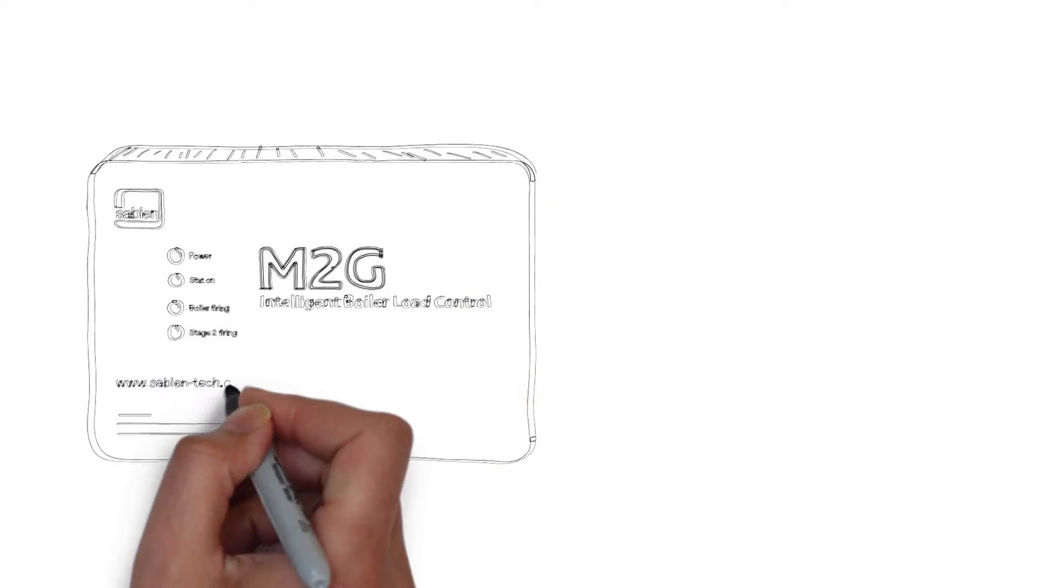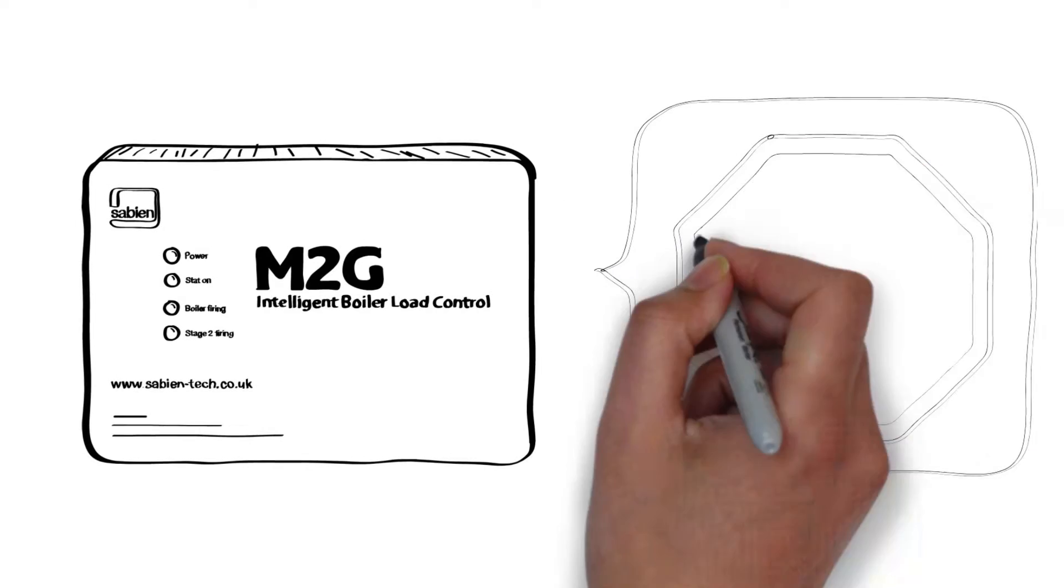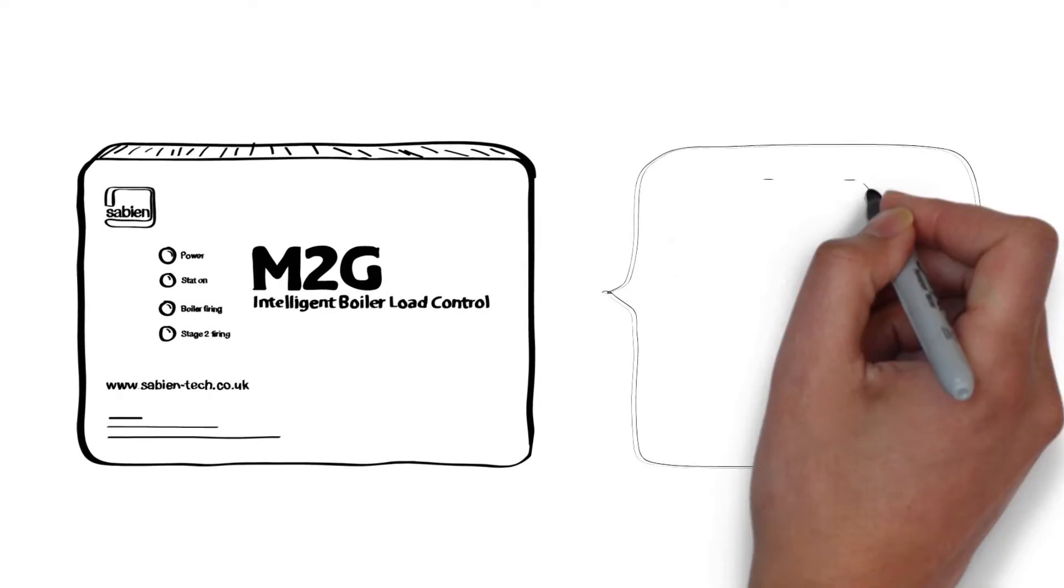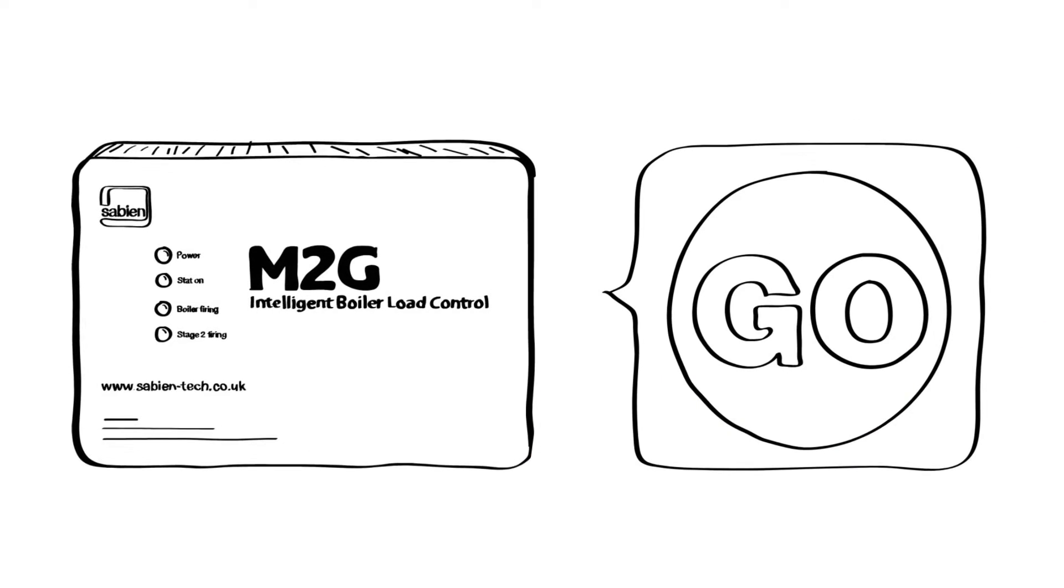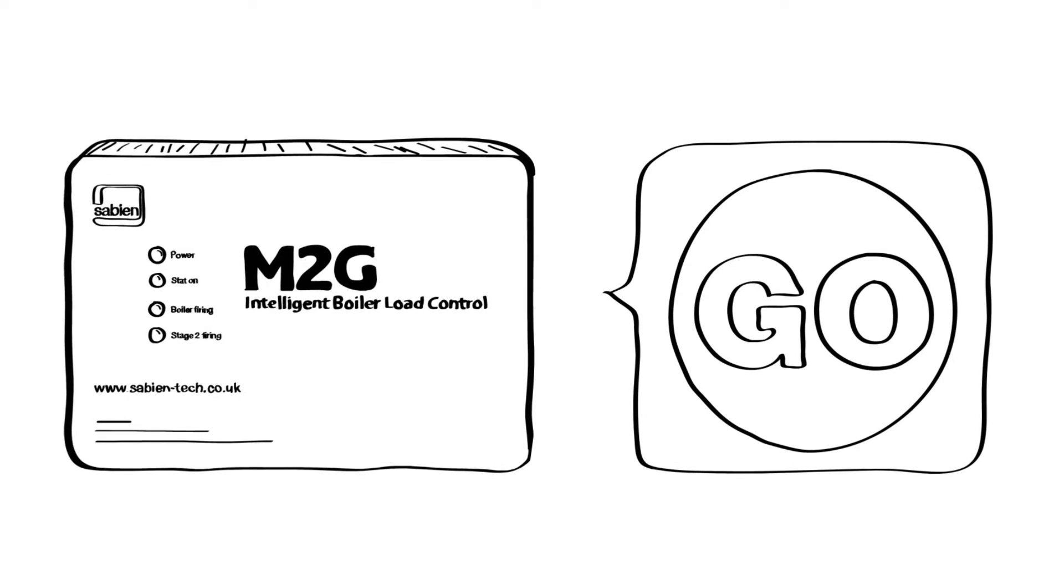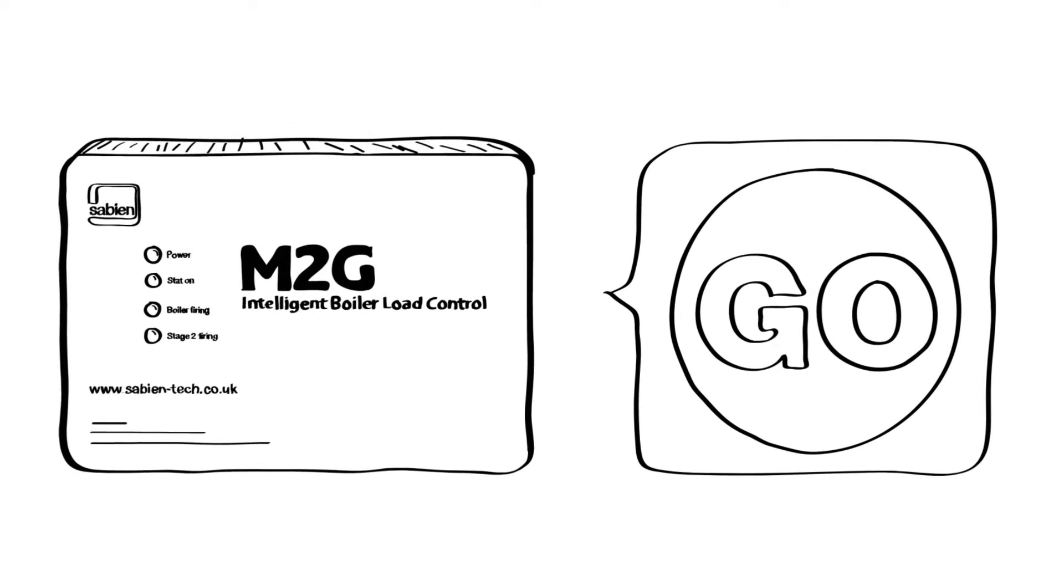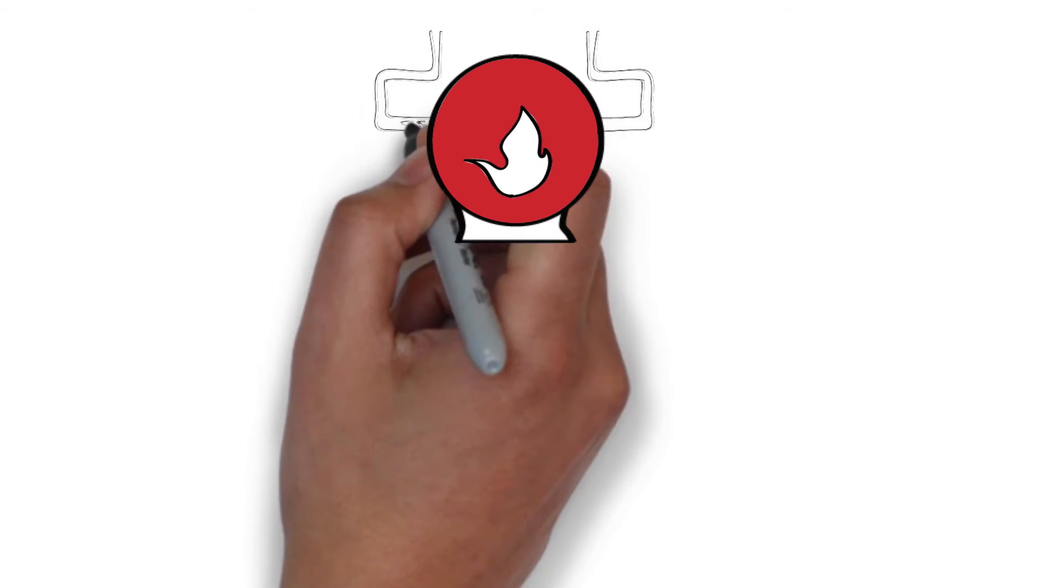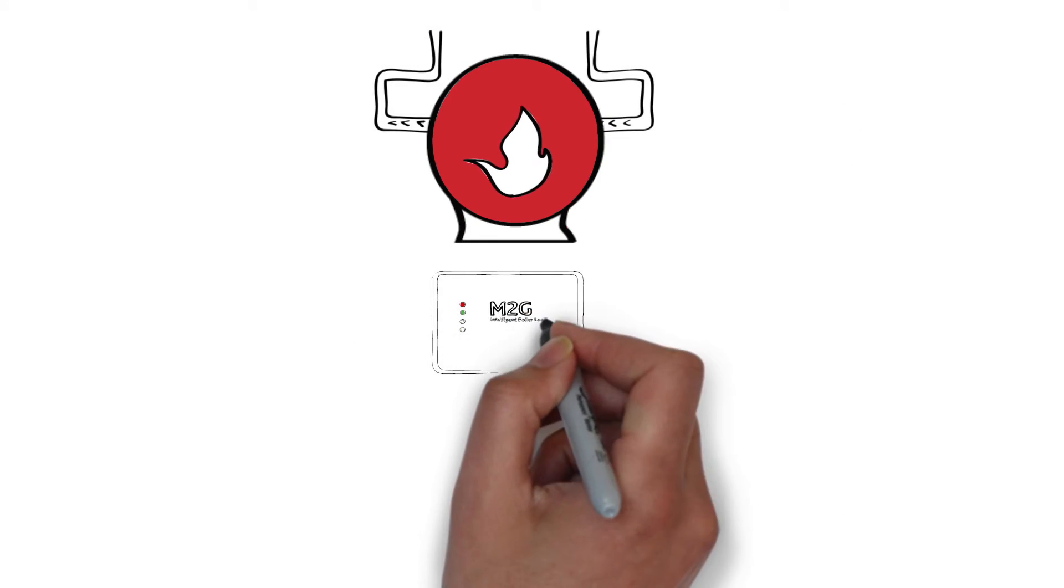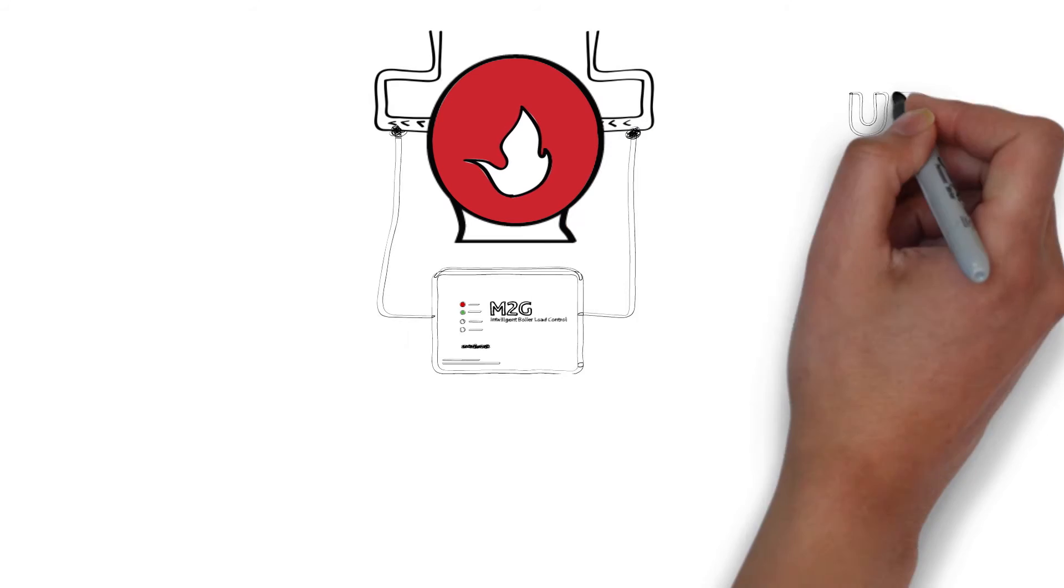M2G works in much the same way, by detecting when it's necessary for the boiler to stop and when to go. By taking measurements every second, the M2G can see if there is a real demand for heat or if the boiler is dry cycling. M2G does this by measuring the boiler's temperature as the water flows out of the boiler and as it returns.